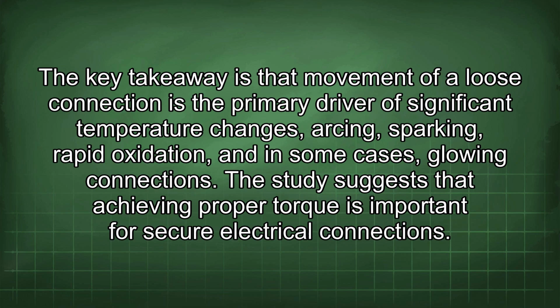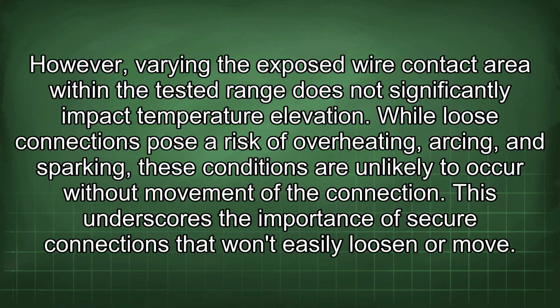The key takeaway is that movement of a loose connection is the primary driver of significant temperature changes, arcing, sparking, rapid oxidation, and in some cases, glowing connections. The study suggests that achieving proper torque is important for secure electrical connections. However, varying the exposed wire contact area within the tested range does not significantly impact temperature elevation. While loose connections pose a risk of overheating, arcing, and sparking, these conditions are unlikely to occur without movement of the connection. This underscores the importance of secure connections that won't easily loosen or move.